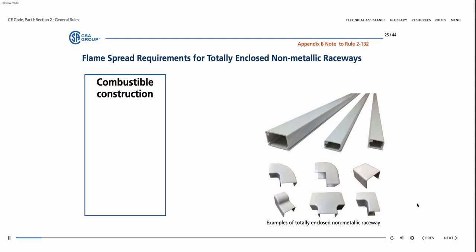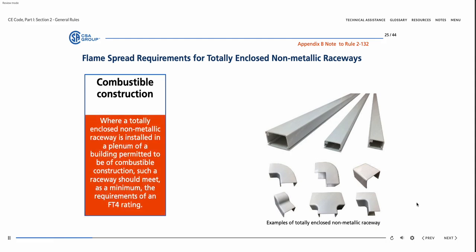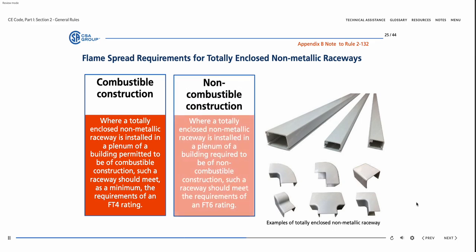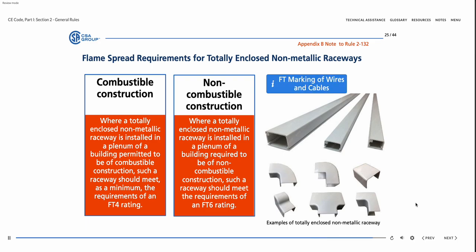Flame spread requirements for totally enclosed non-metallic raceways. When a totally enclosed non-metallic raceway is installed in a plenum of a building permitted to be of combustible construction, this type of raceway should meet, as a minimum, the requirements of an FT4 rating. When a totally enclosed non-metallic raceway is installed in the plenum of a building required to be of non-combustible construction, this type of raceway should meet the requirements of an FT6 rating.